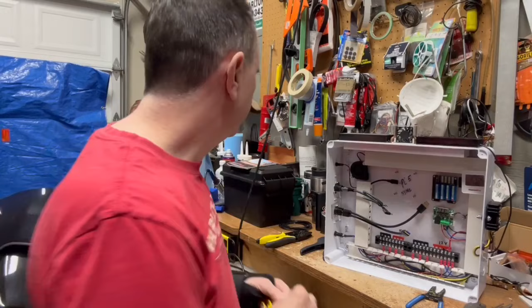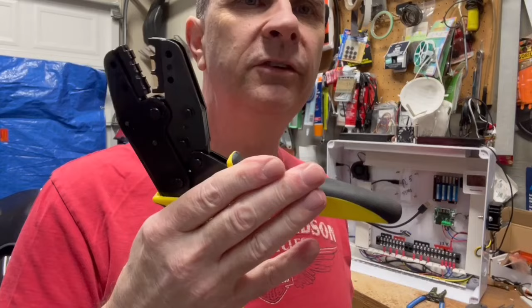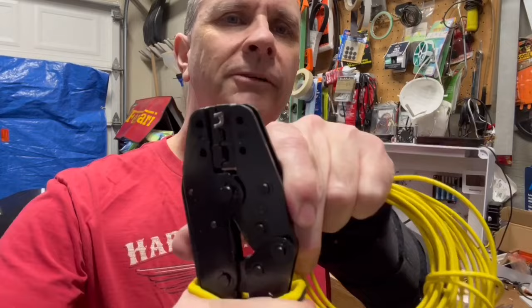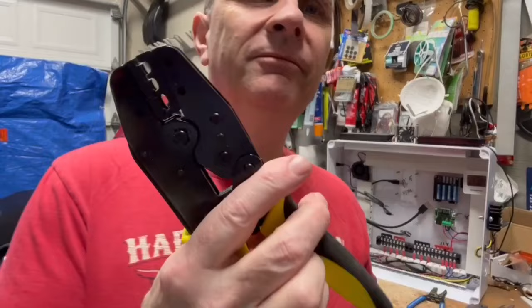The other really good tool to use is a ratchet crimper. You can hear it, and it won't release until you've gone down all the way. Just insert it and crimp, and that sucker's never going to pull off. These things are like 15 to 20 bucks now, so there's no reason not to use them, and you get a perfect crimp every time.